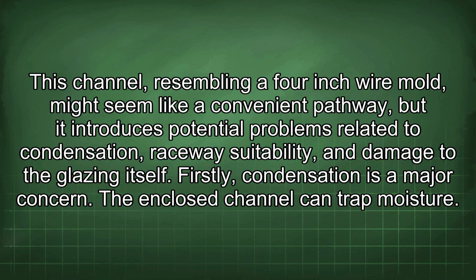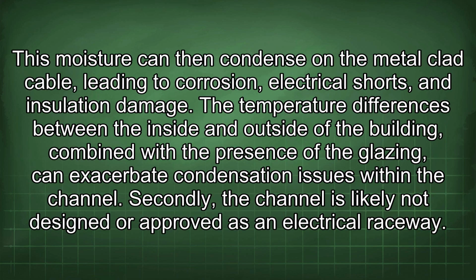Firstly, condensation is a major concern. The enclosed channel can trap moisture. This moisture can then condense on the metal-clad cable, leading to corrosion, electrical shorts, and insulation damage. The temperature differences between the inside and outside of the building, combined with the presence of the glazing, can exacerbate condensation issues within the channel.